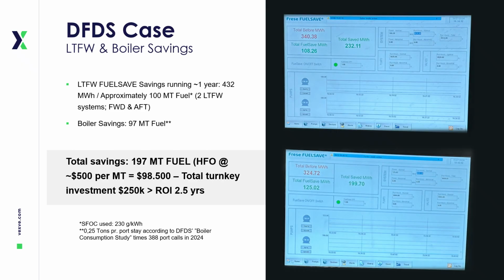This slide shows the verified before and after results from the DFDS case. Over the course of 1 year, optimization of the two low-temperature freshwater systems, forward and aft, delivered 432 megawatt-hours of energy savings. That equals approximately 100 metric tons of fuel saved, calculated using a specific fuel oil consumption of 230 grams per kilowatt-hour. In addition, boiler optimization generated a further 97 metric tons of fuel savings. This figure is based on DFDS's own boiler consumption study, assuming 0.25 tonnes per port stay across 388 port calls in 2024. Together, these measures provided a total saving of 197 metric tonnes of fuel.